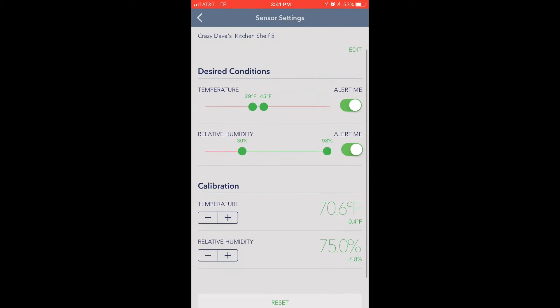How do you raise and lower the temperatures? Very simple: scroll all the way down, click on each of the individual sensors, and hit configure. You'll see what says calibration - it's plus or minus. So on temperature, you plus or minus until you get to 32. On relative humidity, same thing, plus or minus as needed.